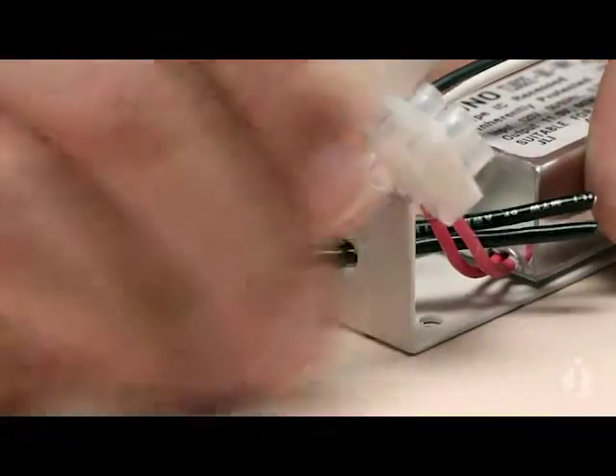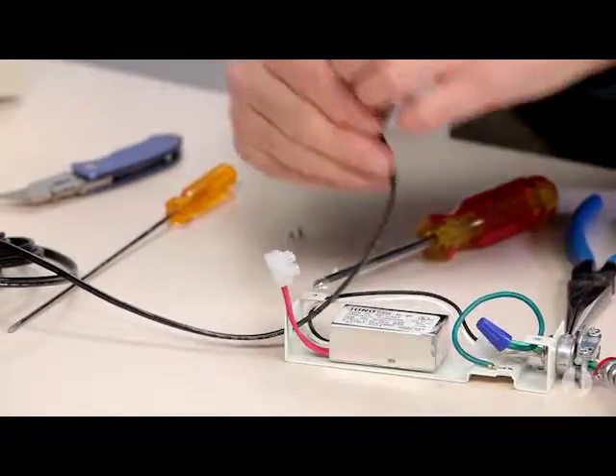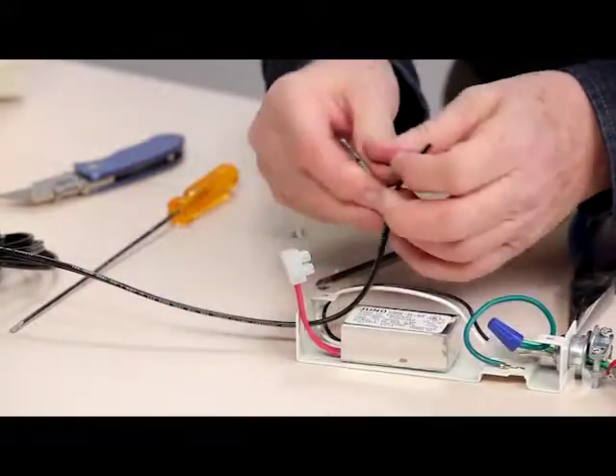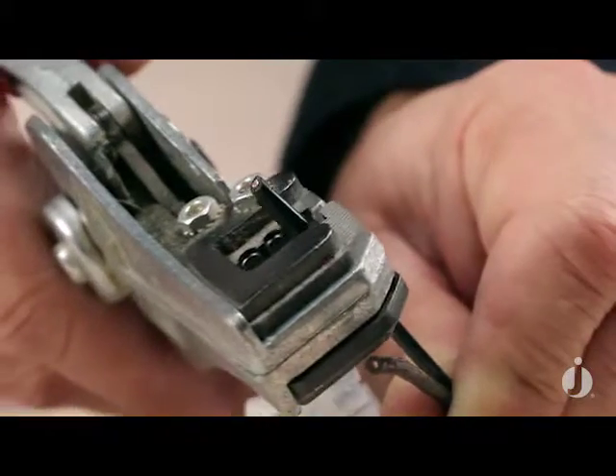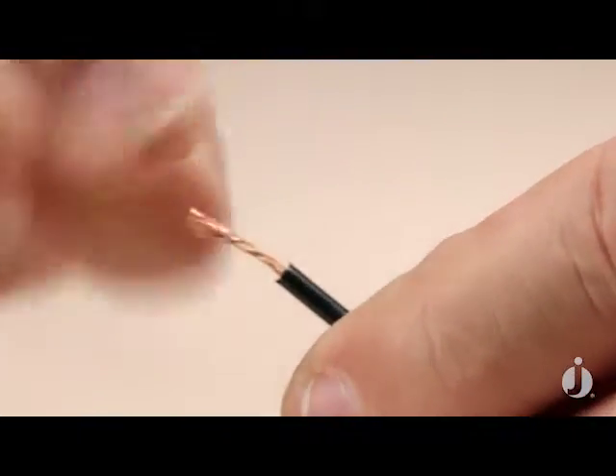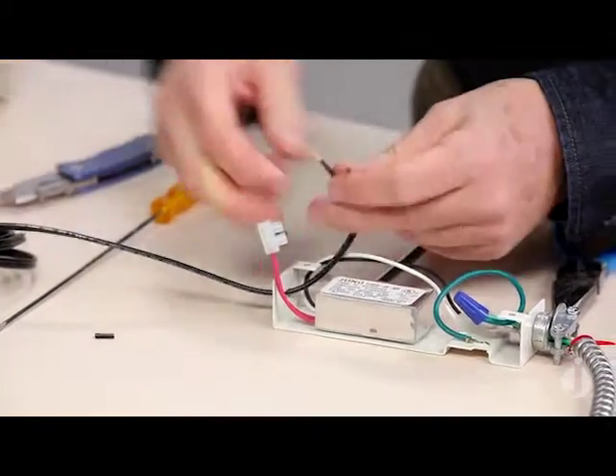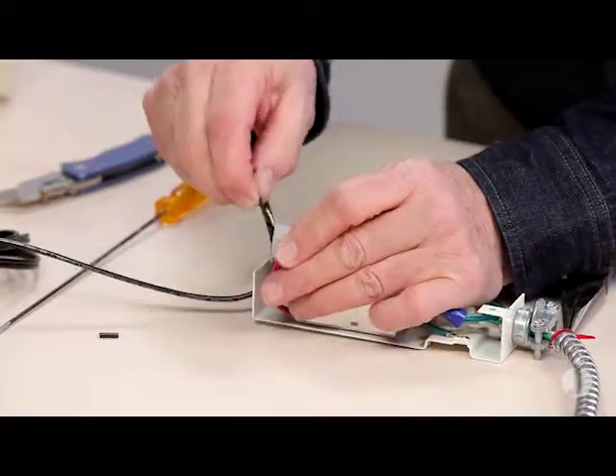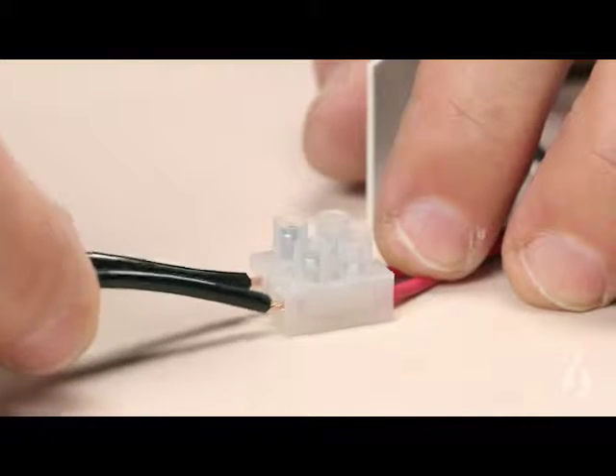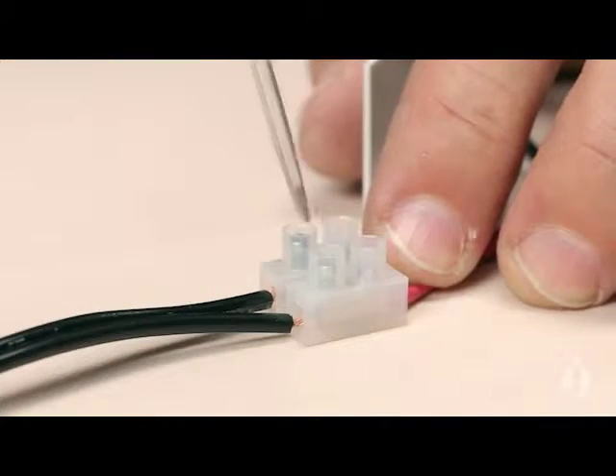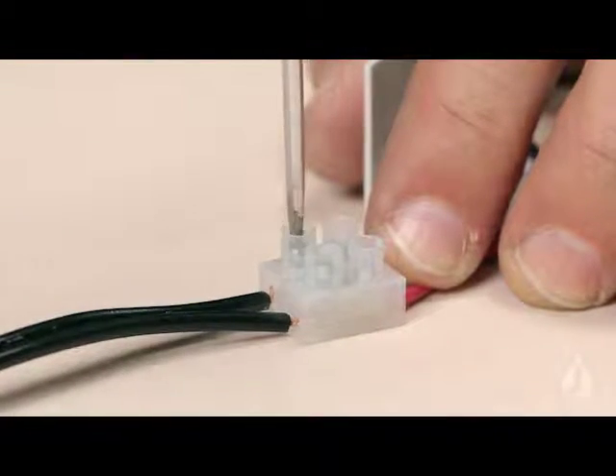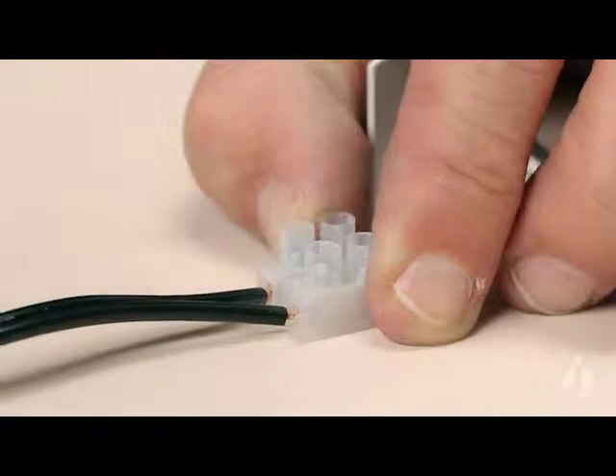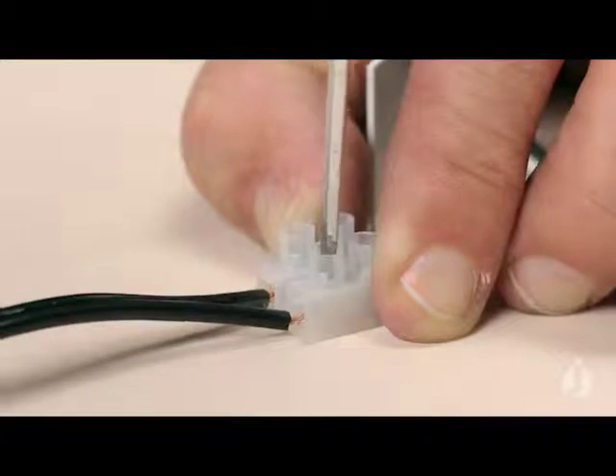So I'm going to split those wires and feed them through that oval-shaped hole. These are the wires that, of course, connect to my load. And I'll strip those. You may notice here there's no black wire and white wire. We just have two red wires going into two black wires. With low voltage systems, we are not required to observe any kind of polarity. I'm tightening the screw now down onto my first wire and my second wire coming next.